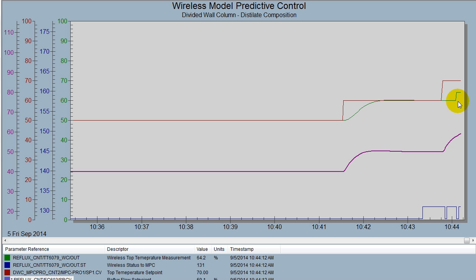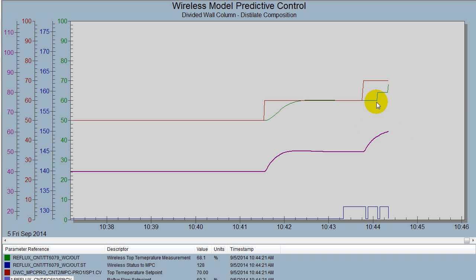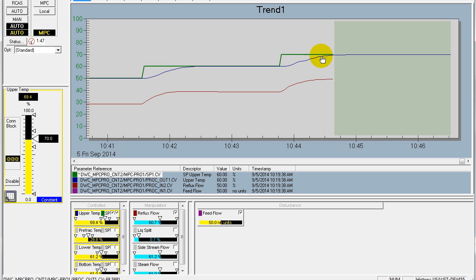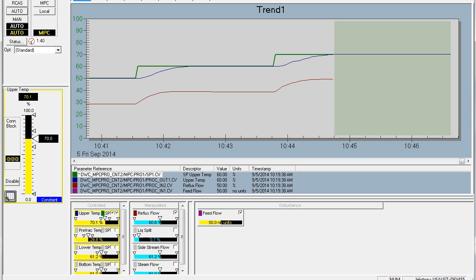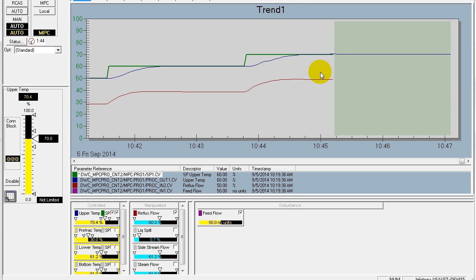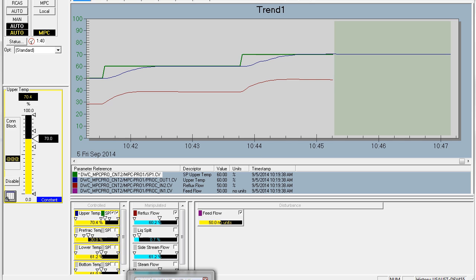If we look at the actual measurement itself, this trend shows the true wireless measurement, and you notice that it changes very infrequently. In between changes in the measurement, model predictive control automatically uses the simulated value of the temperature based upon the status calculated by the composite we saw earlier in our control loop. At the points where we get a new measurement, you'll notice a little bit of deviation on the response showing the update correcting for the model. The integral of absolute error is a little worse, but for this entire control we only used four new communications versus 87 previously with the wired measurement.